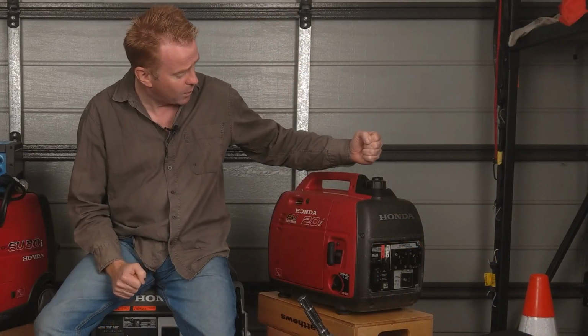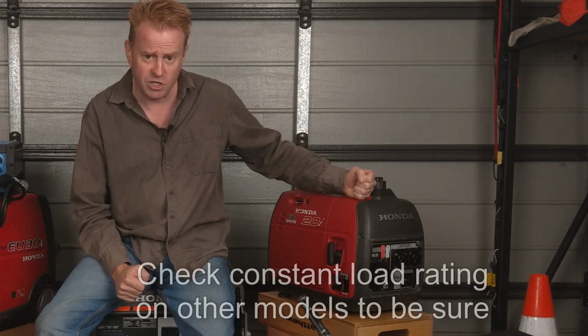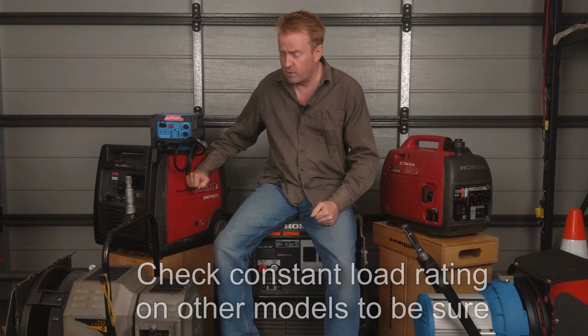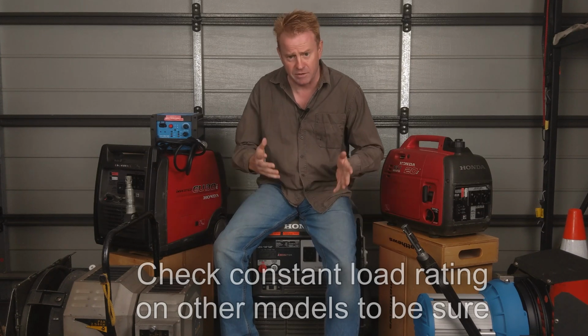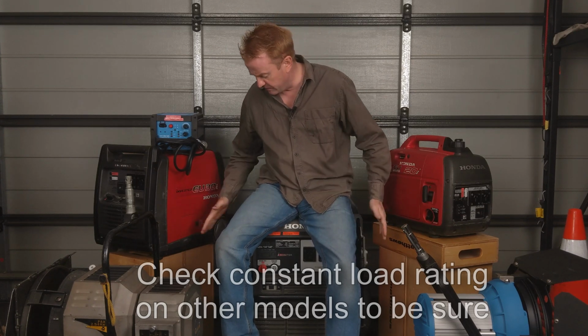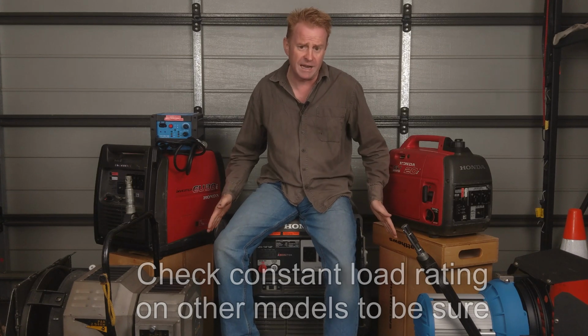You can run a 1.2K HMI if it's power factor corrected off a 2 kVA generator. Off a 3 kVA generator, you can run an M18 if it's power factor corrected. And the 7 kVA I'm sitting on will run easily a 4K power factor corrected HMI.